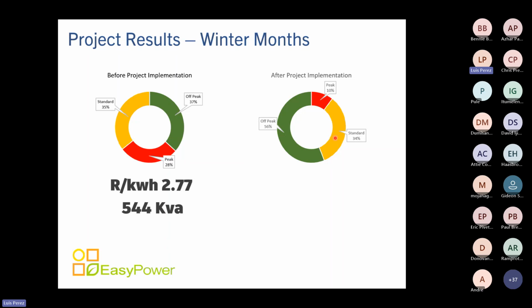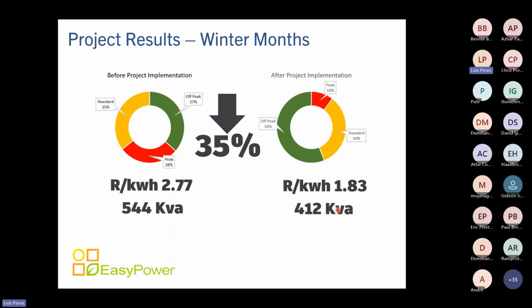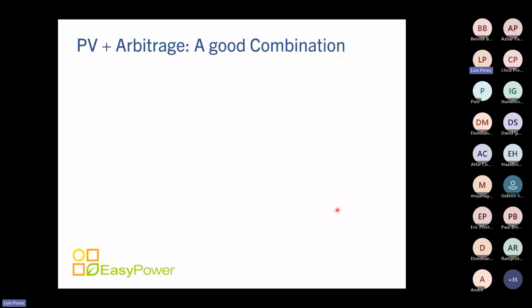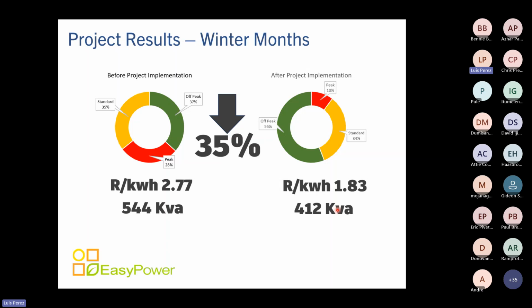Your typical cost, if you exclude the inverter, of solar modules, structures, carports, just the bill of materials to make power, the levelized cost of energy, is close to 0.7, 0.8 rand per kilowatt hour, which is vastly less than the cost of standard energy. Therefore, it makes sense to send all that energy to the battery to offset peak energy. So what is the end result? Your cost of energy goes down to 1.83 rand per kilowatt hour at today's rates. And you will have a demand reduction of approximately 120, 130 kVA, which is a lot more valuable than the energy itself, if you put it into the equation. So it's a total reduction of 35% in peak energy consumption for this complex.